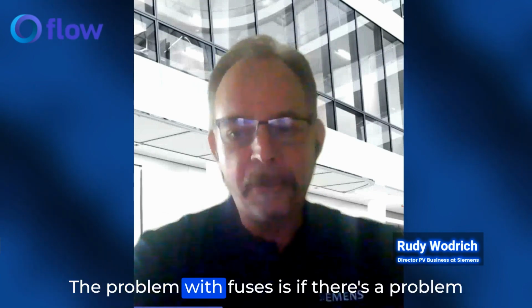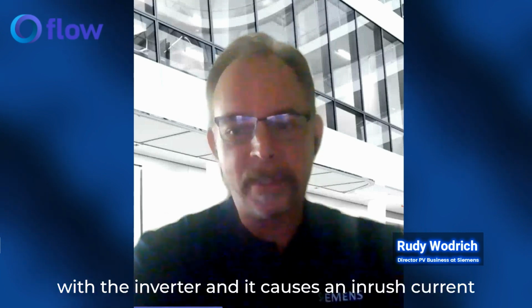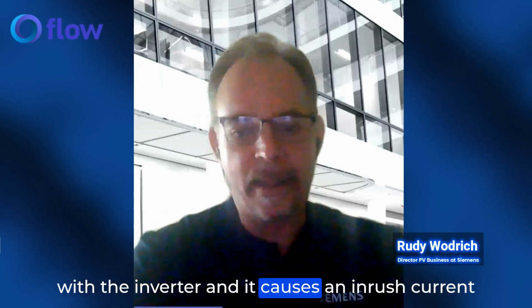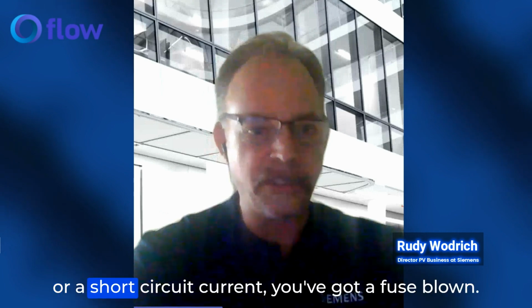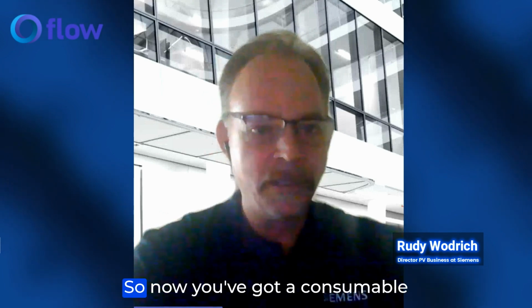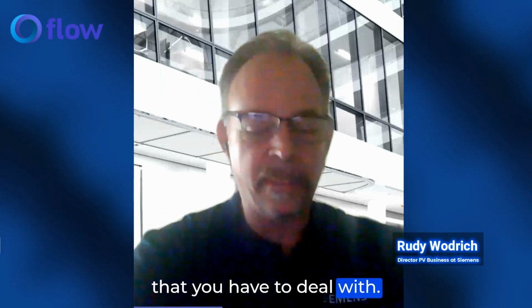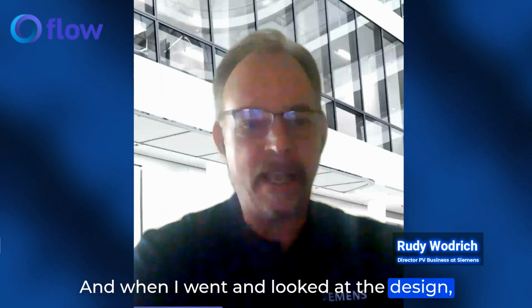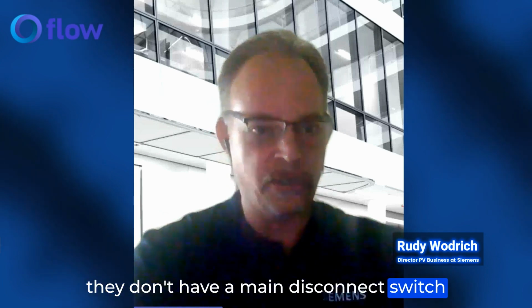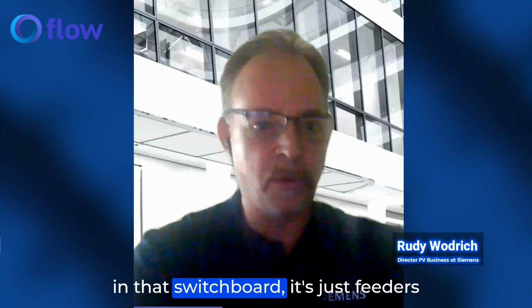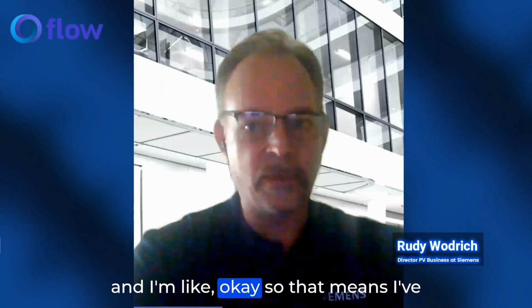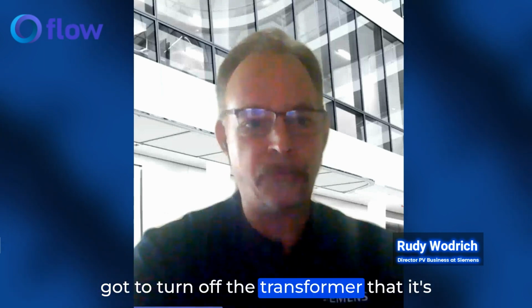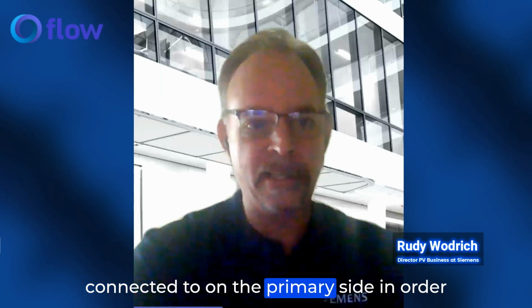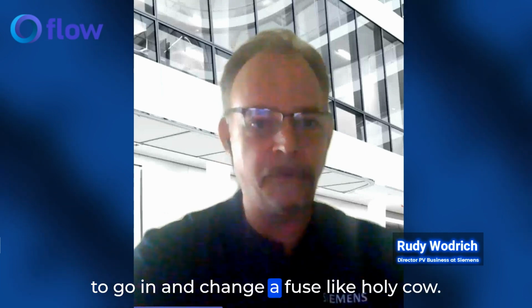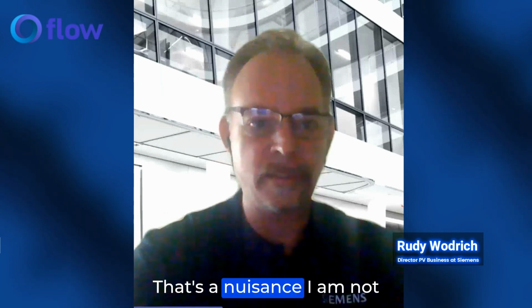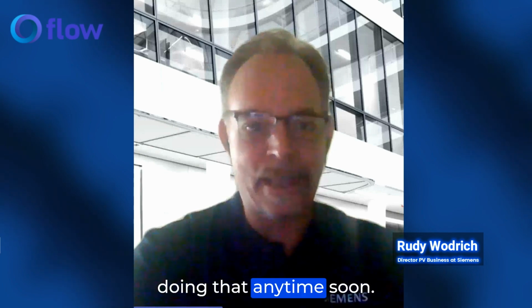The problem with fuses is if there's a problem with the inverter and it causes an inrush current or a short circuit current, you've got a fuse blown. So now you've got a consumable you have to deal with. And when I went and looked at the design, they don't have a main disconnect switch in that switchboard, it's just feeders. So that means I've got to turn off the transformer on the primary side just to go in and change a fuse. Holy cow, that's a nuisance. I am not doing that anytime soon.